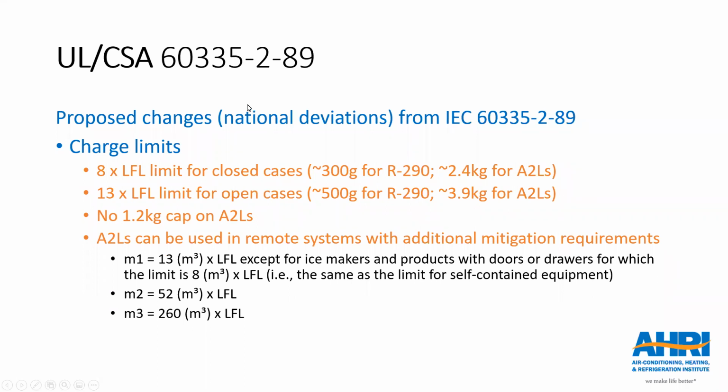So there are also some proposed changes to the flammable refrigerant charge limits. For closed equipment with doors or drawers, only 8 times LFL is allowed. This is approximately 300 grams of R290 and around 2.4 kilograms for a typical A2L refrigerant. For open cases, the charge limit remains at 13 times LFL, or about 500 grams of R290 or about 3.9 kilograms of an A2L. Due to the AHRI research projects on A2L refrigerants that are going to be covered later in this webinar, the 1.2 kilogram cap on A2Ls has been removed.